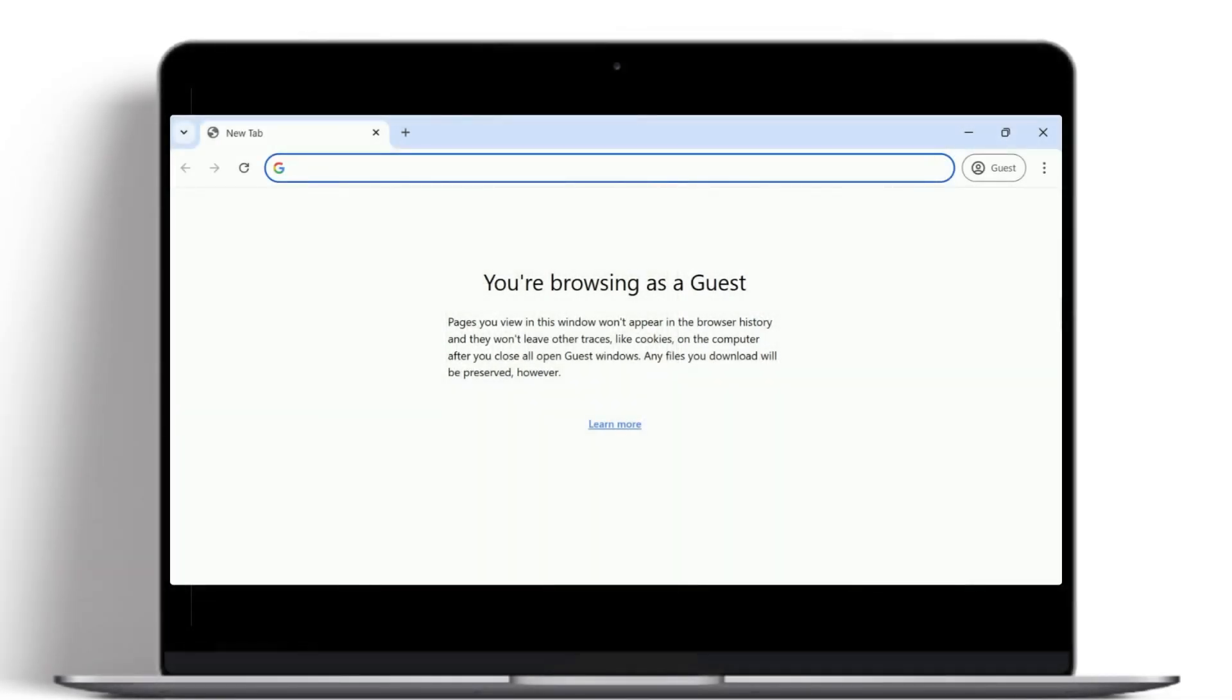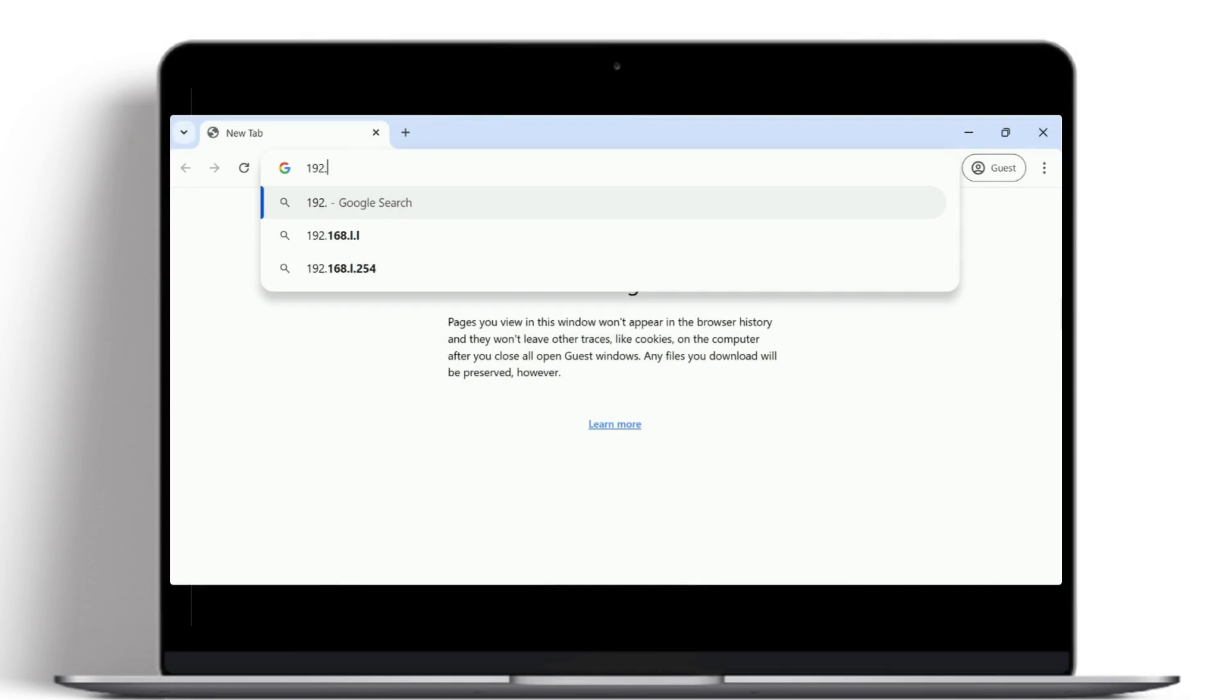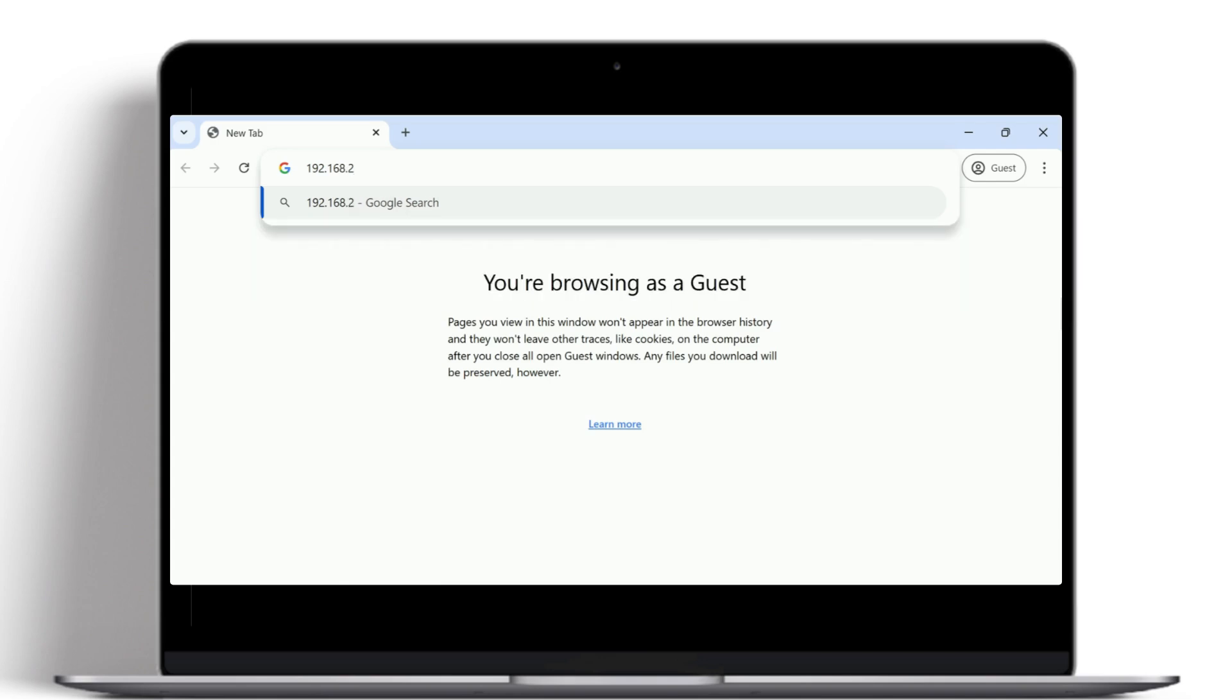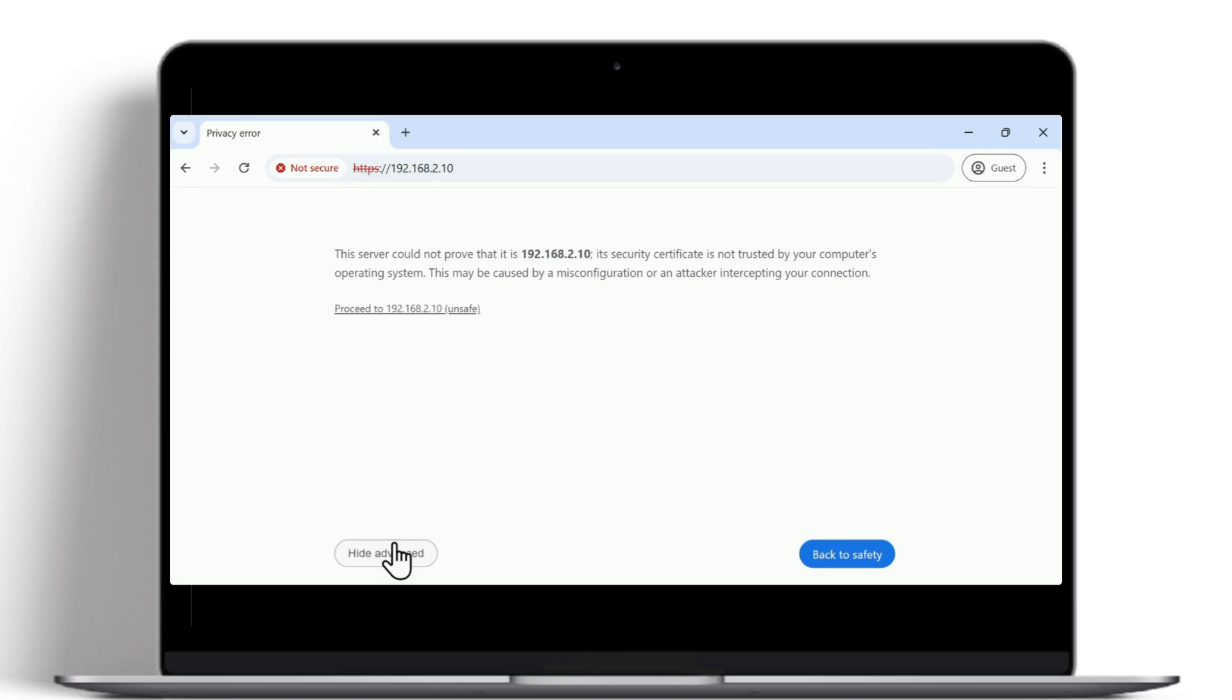Logging in to WebHMI. Open a web browser and type the Protection Relay's IP address in the address bar and press Enter. In this example, we are using the default rear port IP address 192.168.2.10. Acknowledge the login banner notification if displayed.